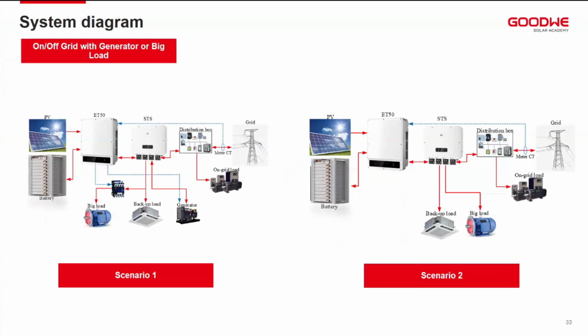Now, if we look into other scenarios, we have the scenarios where we're including the on-grid loads. Scenario one is, on-grid loads, you have your diesel generator, you have your critical loads, and within the same critical load output, you have another big load that's connected to, well, there's a contactor in between the big load and the backup port.